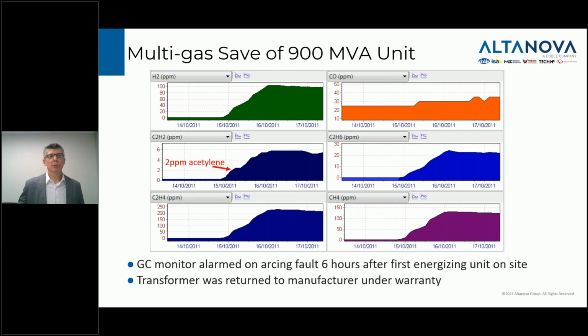This was a case where a very sensitive multi-gas monitor was able to pick up an early fault in acetylene when it was less than a couple of ppm. This turned out to be a happy story for the owner. They de-energized and did a bunch of other diagnostic tests, and ultimately the OEM was called in, did a teardown, and the transformer was returned to the manufacturer under warranty. The fact that this monitor was there giving timely data prevented a lot of cost and risk to that operator.